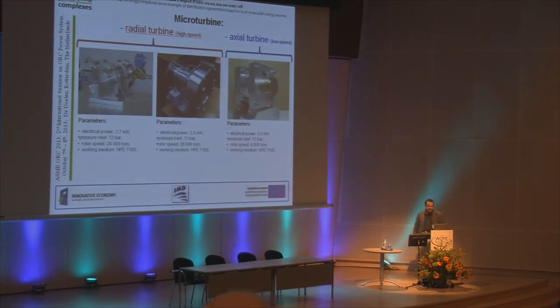We designed and built two types of microturbines: a two-stage radial turbine, which is a high-speed turbine, and one axial turbine. The radial turbine has electric power of about 2.7 kilowatts, and the axial turbine about 3.3 kilowatts; the slower speed turbine runs at about 8,000 RPM.